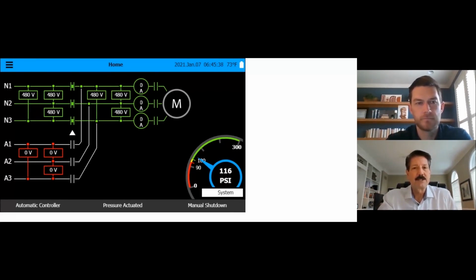Predominantly when you get into situations where you do have something freeze, you get a sensing line freezes, it happens overnight. Things happen, people blame the controller all the time, and then we find out, well, no, it dropped down to like 17 degrees Fahrenheit, and that's why we froze and the pressure transducer went bad. But by morning, maybe it's thawed out or something, but it causes problems. So having a pump room temperature really helps minimize that. It gives us more data, and that, again, is a standard feature. It's actually built into the fascia of the V2 housing itself in the front.